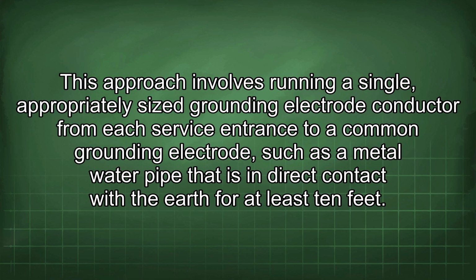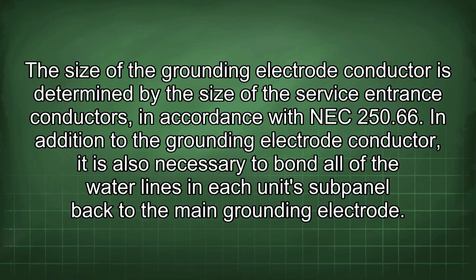a common grounding electrode, such as a metal water pipe that is in direct contact with the earth for at least 10 feet. The size of the grounding electrode conductor is determined by the size of the service entrance conductors, in accordance with NEC 250.66.